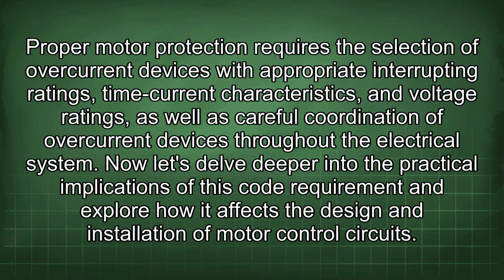Proper motor protection requires the selection of overcurrent devices with appropriate interrupting ratings, time current characteristics, and voltage ratings, as well as careful coordination of overcurrent devices throughout the electrical system. Now let's delve deeper into the practical implications of this code requirement and explore how it affects the design and installation of motor control circuits.